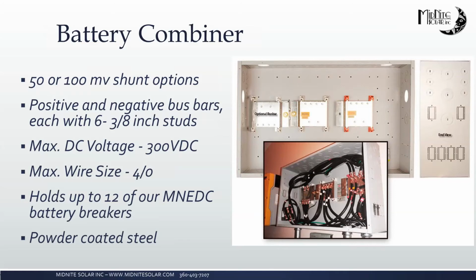The positive and negative bus bars, as you see included, there's one white and one red. Those are pretty massive tin-plated copper bus bars. They have 6 studs pre-attached that are 3/8 of an inch in diameter. You can drill the plate for additional fastening, and you can double lug the wires as shown in the picture below. You can also add the optional negative bus bars. So if you're using this as an example, the picture below, you'll see we're bringing in 4 strings of batteries, and we're feeding a handful of inverters and loads. So they have a bus bar on each side just to make it more convenient.